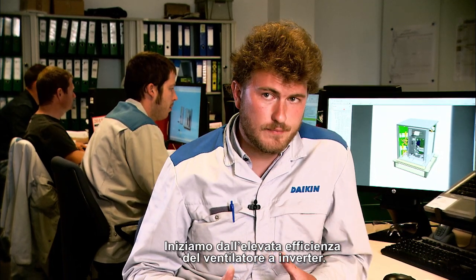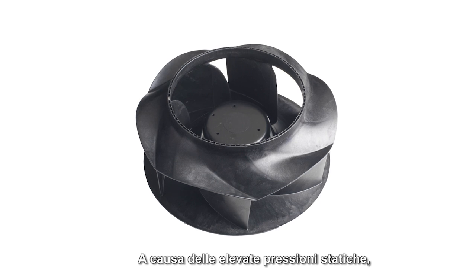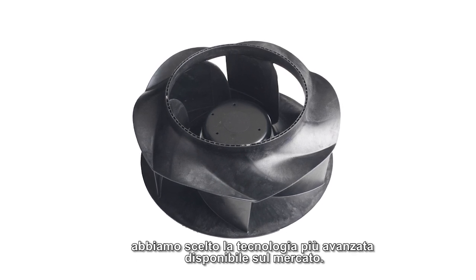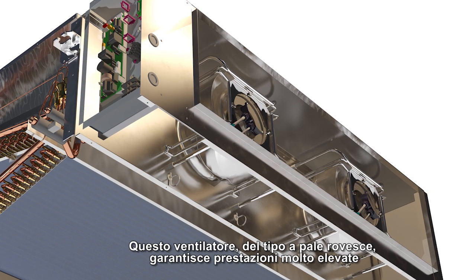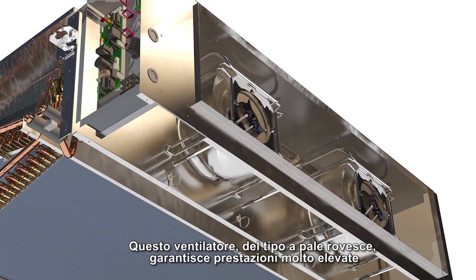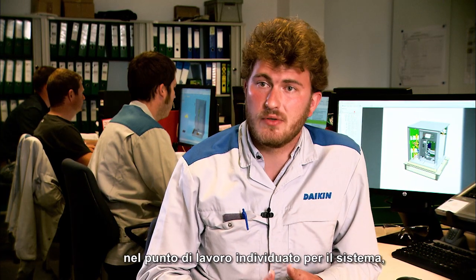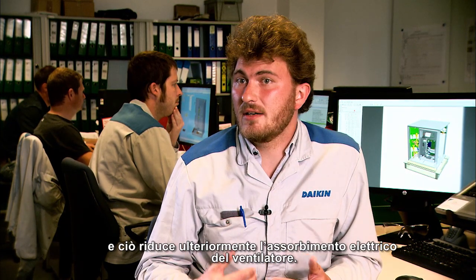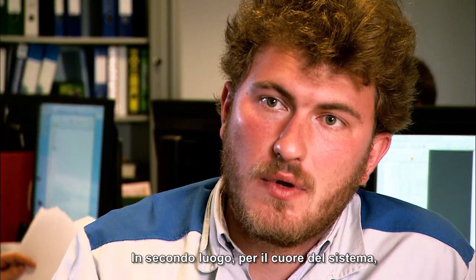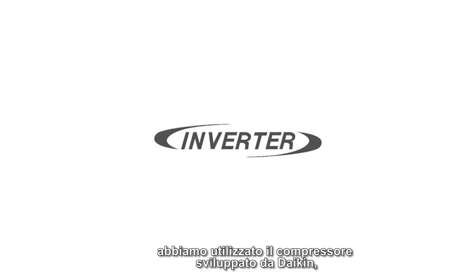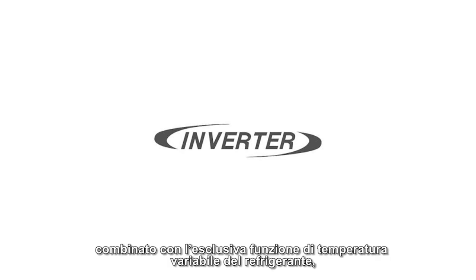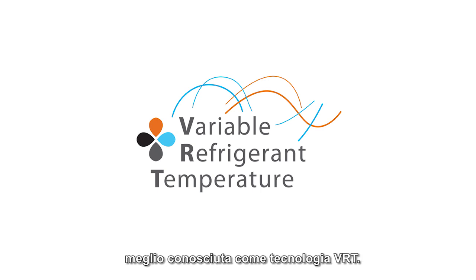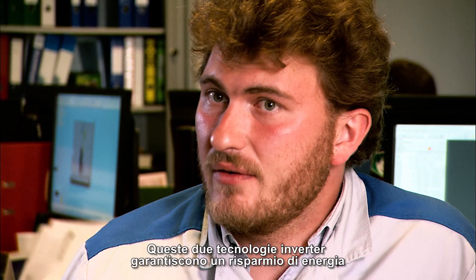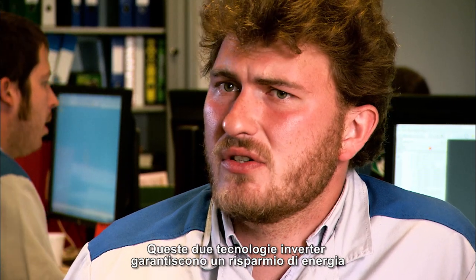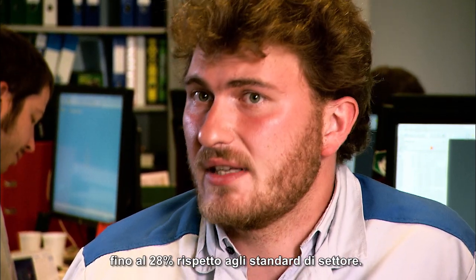Let's start with the high efficiency inverter driven turbofan. Due to this high static pressure situation, we selected the latest fan technology available on the market. These backward curved turbofans have a very high performance at the required operation point of the unit, thus further decreasing the power input to the fans. Secondly, for the heart of our system, we use our Daikin developed compressor technology combined with our unique variable refrigerant temperature, better known as VRT technology. These two inverter technologies deliver energy savings of up to 28% compared to the industry standard.